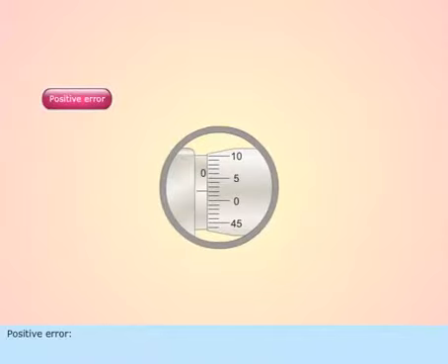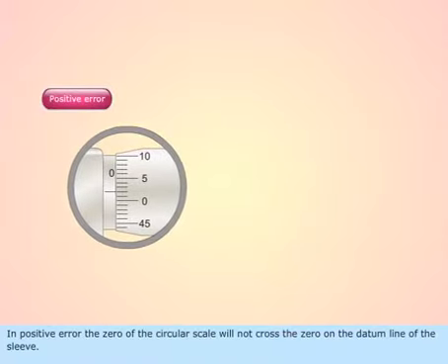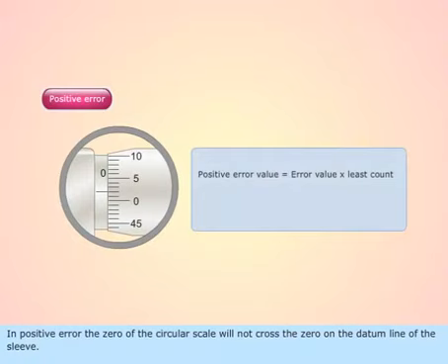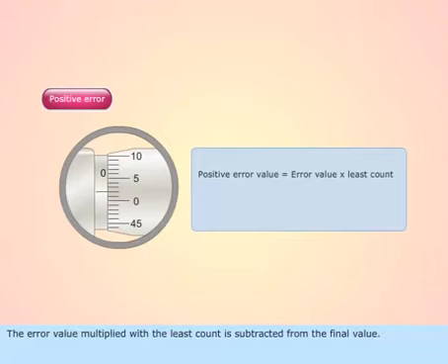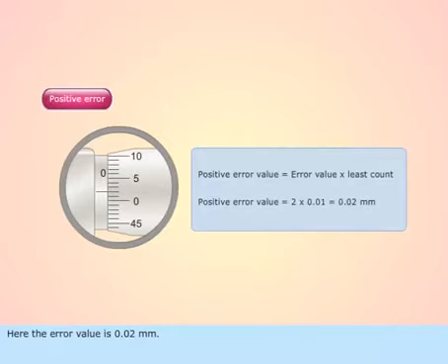In positive error, the zero of the circular scale will not cross the zero on the datum line of the sleeve. The error value multiplied with the least count is subtracted from the final value. Here the error value is 0.02 mm.